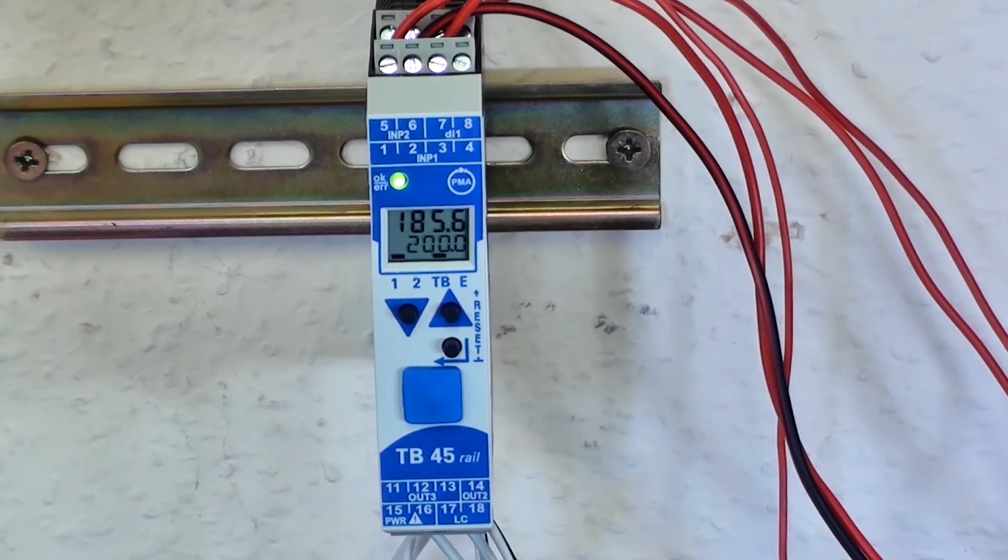TB45-2 is a temperature limiter. Temperature limiters use a latching output relay requiring a local or remote reset before operation is resumed.